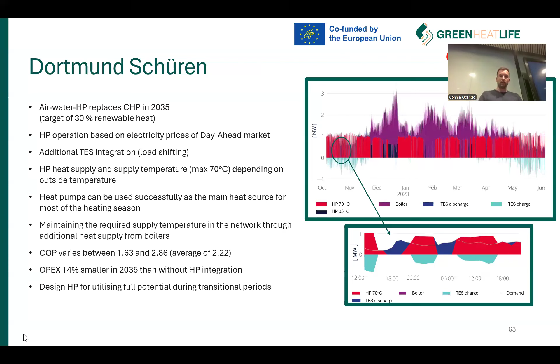However, all in all, the optimization showed us that with the heat pump installed in combination with thermal energy storage, we can reach a COP of 2.2 on average. Of course, a little bit higher in summertime or spring and autumn, but a little bit lower in wintertime, around 1.6, but quite good on average for an air-sourced water heat pump. The first evaluation of economic benefits showed us that we can save operational expenditures of 14% in contrast to not installing a heat pump. So installing the heat pump in the future will have economic benefits and not only ecological ones, so not only reaching the renewable share we have to reach, but also from an economic point of view, it is very beneficial for us.